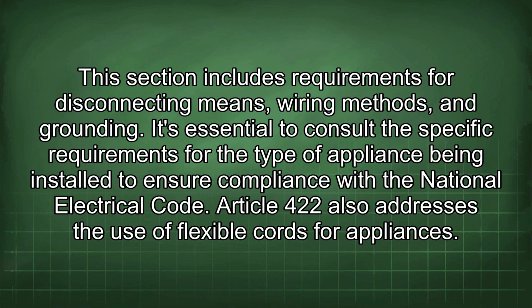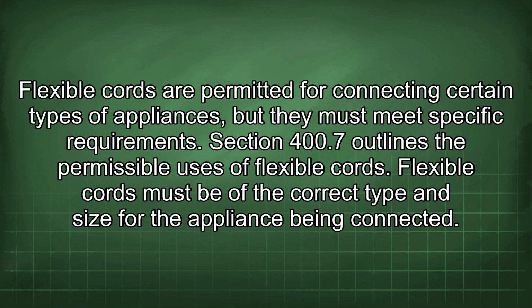It's essential to consult the specific requirements for the type of appliance being installed to ensure compliance with the National Electrical Code. Article 422 also addresses the use of flexible cords for appliances. Flexible cords are permitted for connecting certain types of appliances, but they must meet specific requirements. Section 400.7 outlines the permissible uses of flexible cords. Flexible cords must be of the correct type and size for the appliance being connected.